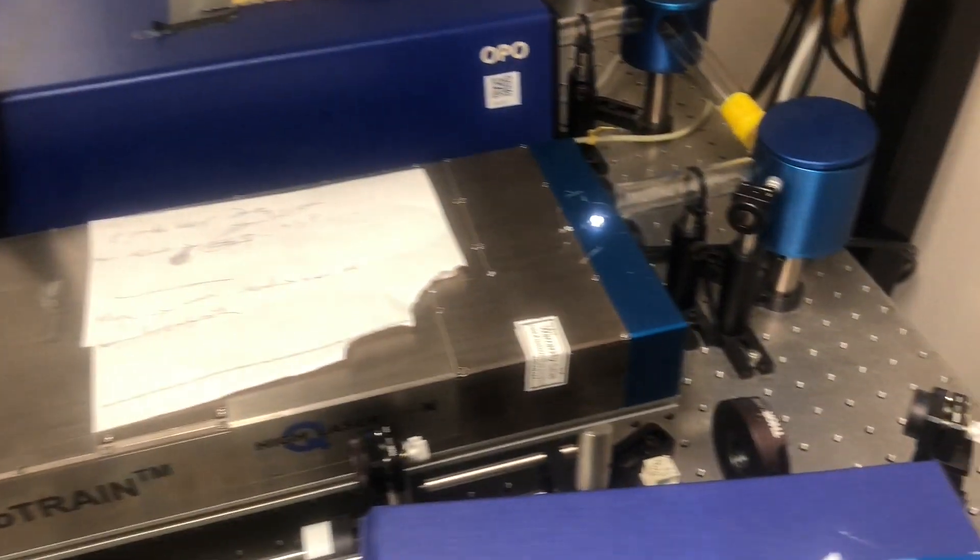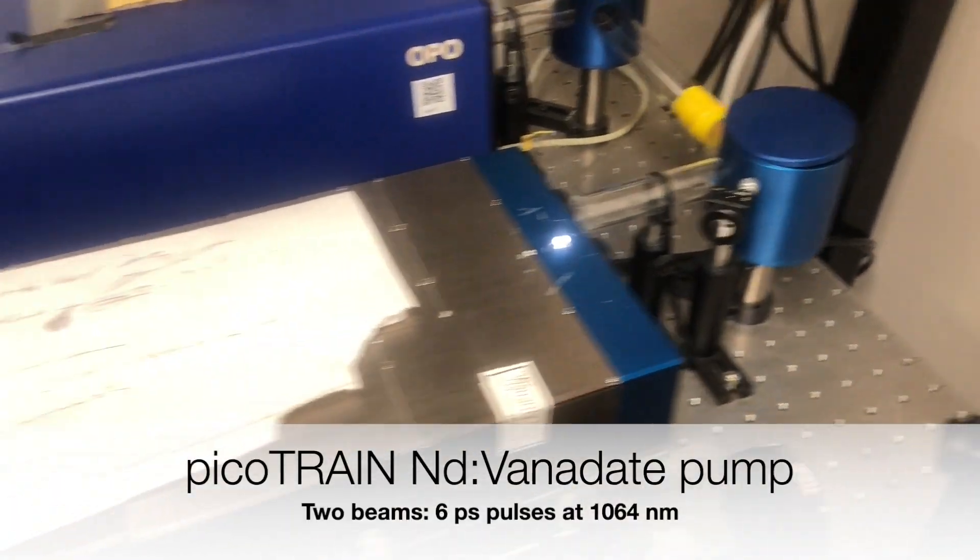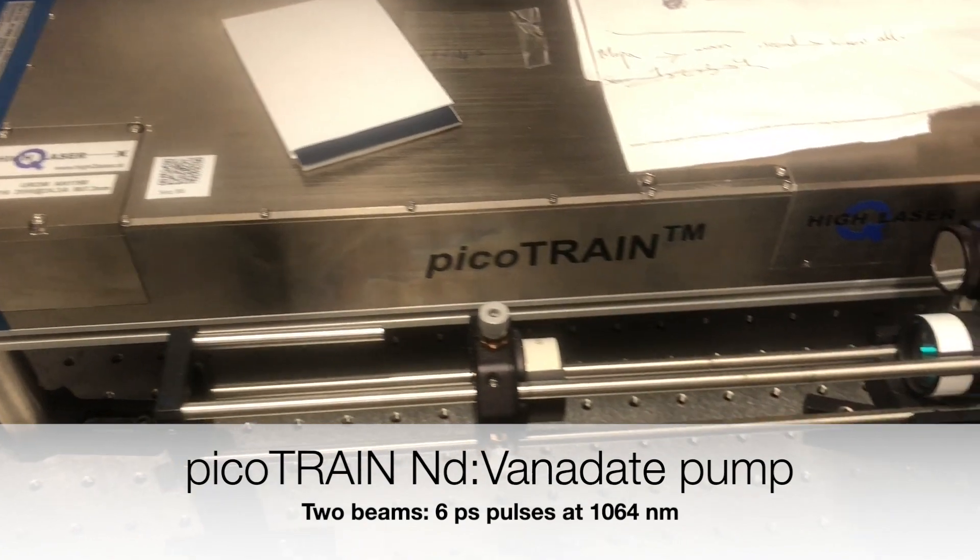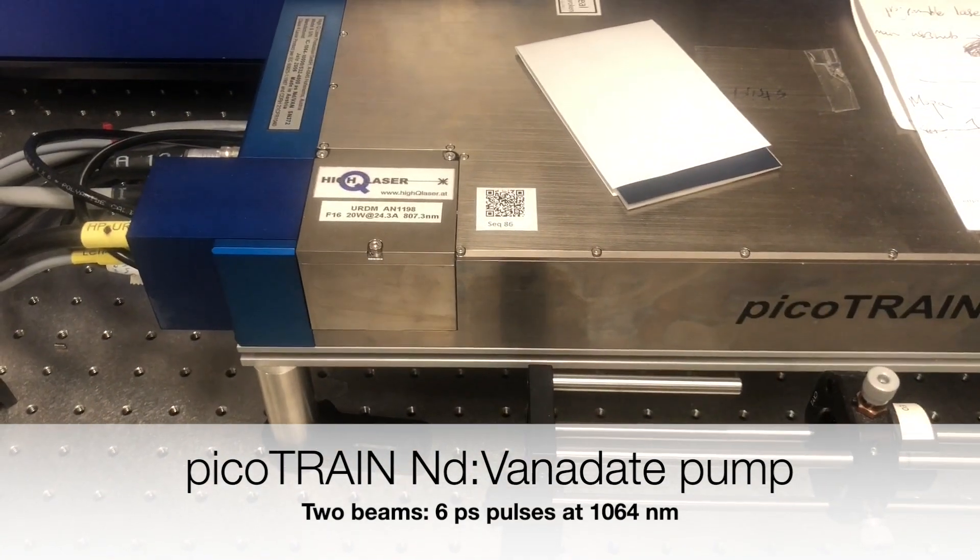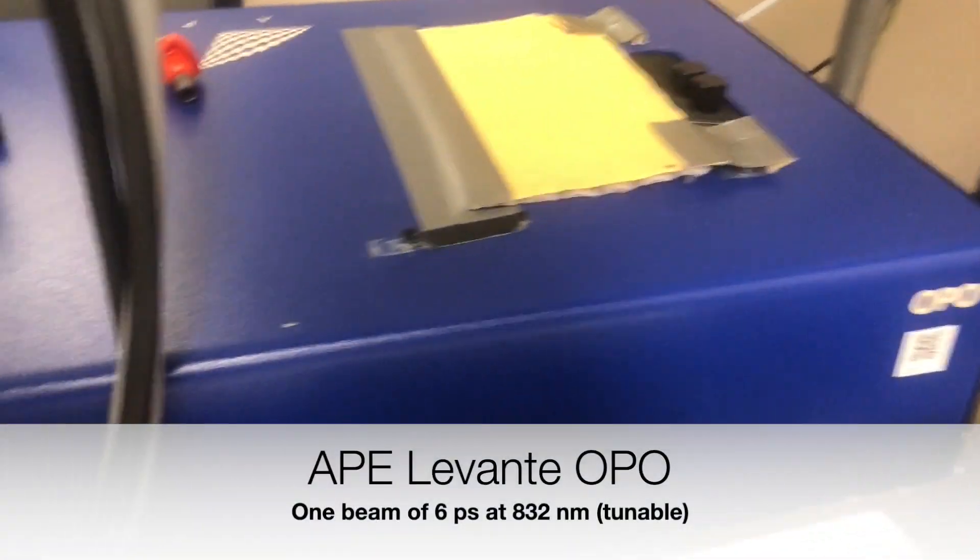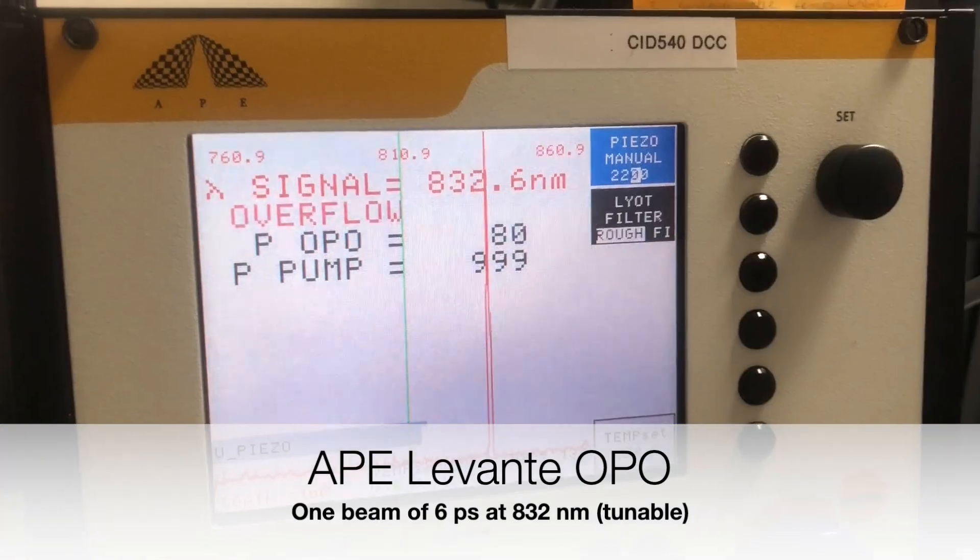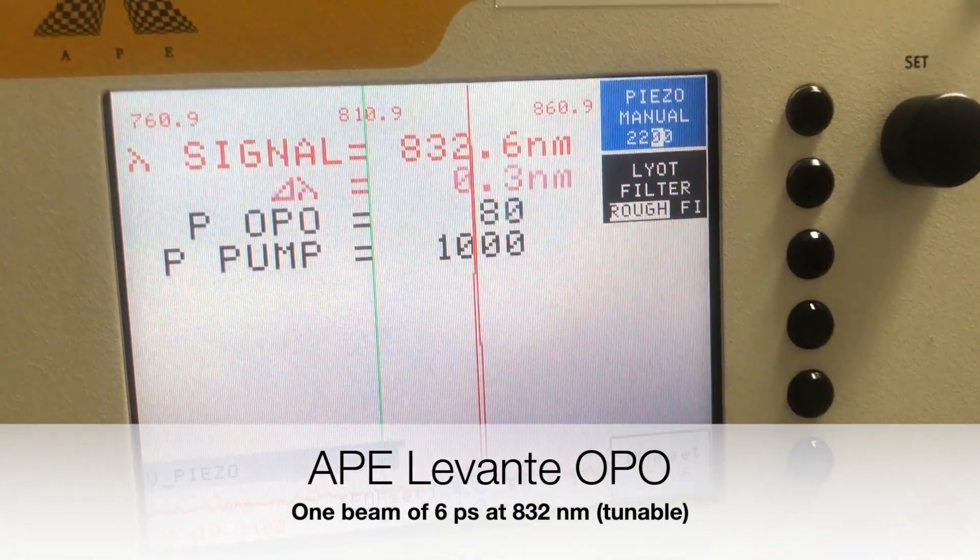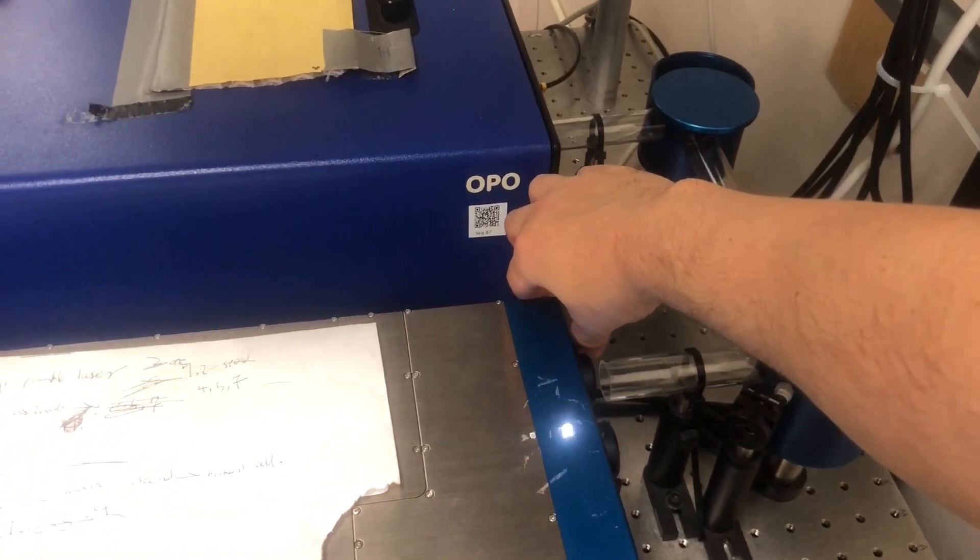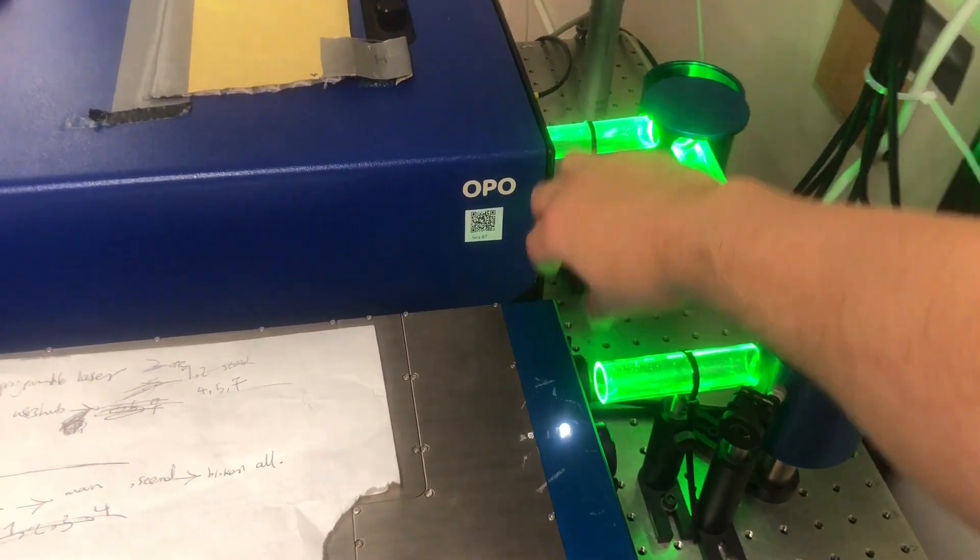First things first, let's turn on the laser. We're going to be using a Picotrain that generates 1064 nanometer light with an optical parametric oscillator from APE in Germany called the Levante. The OPO generates a beam at 832 nanometers. The Picotrain has an output at 532 to pump the OPO, but we're going to be using the main beam at 1064 nanometers.